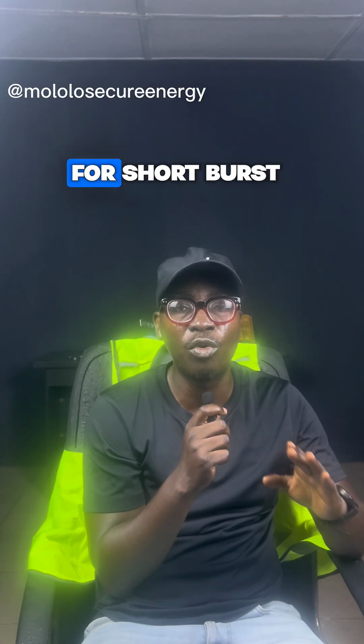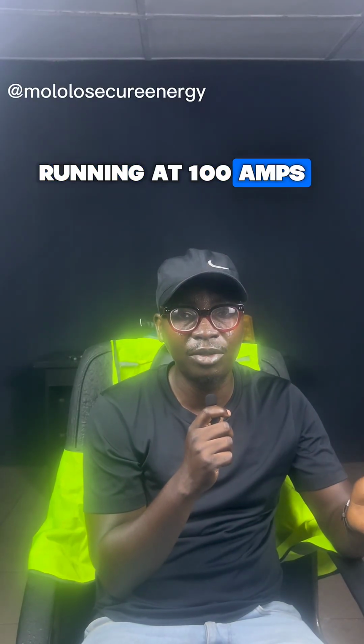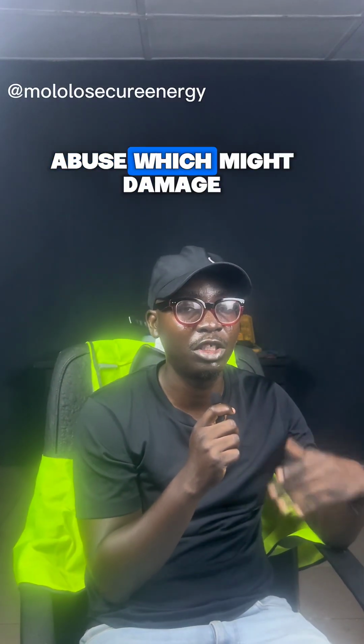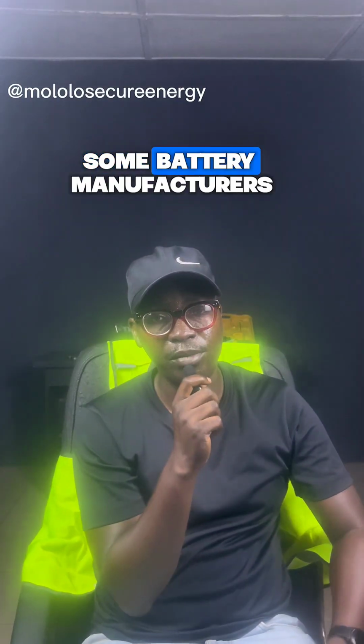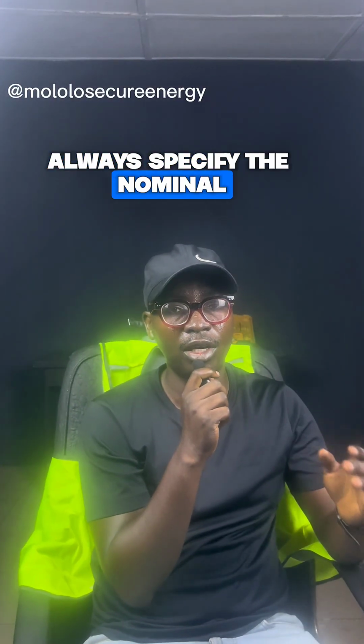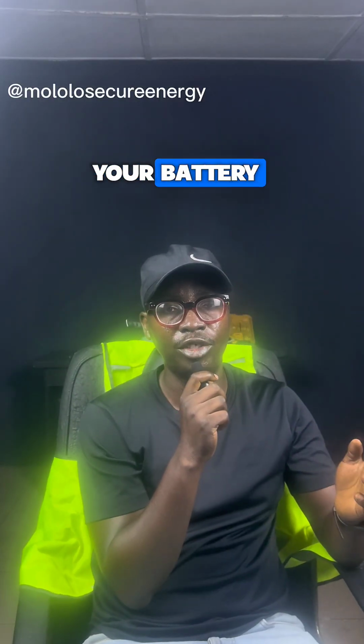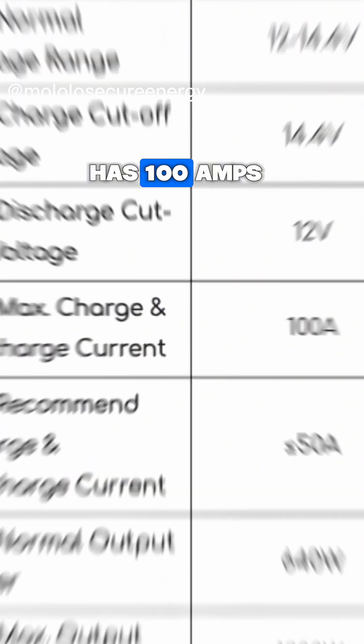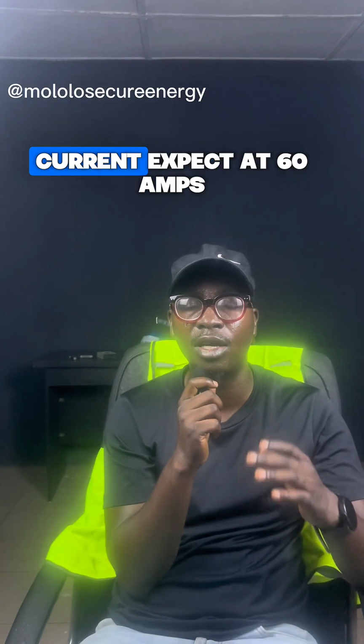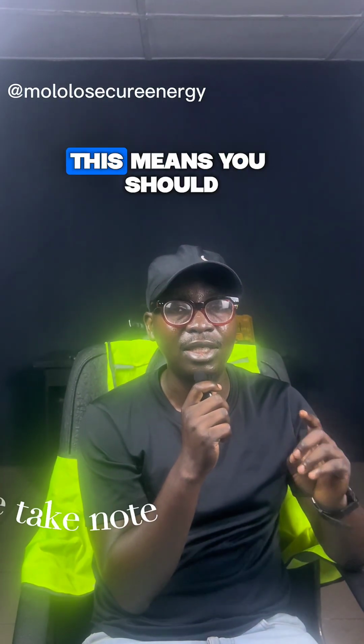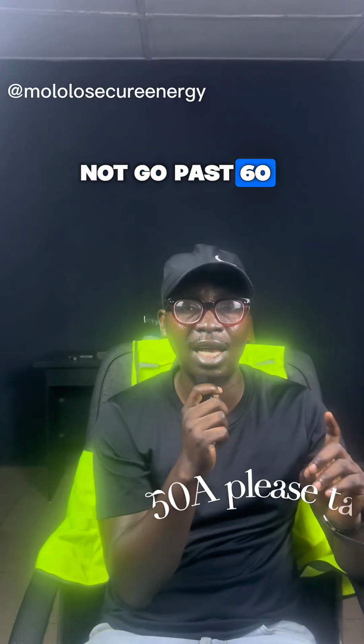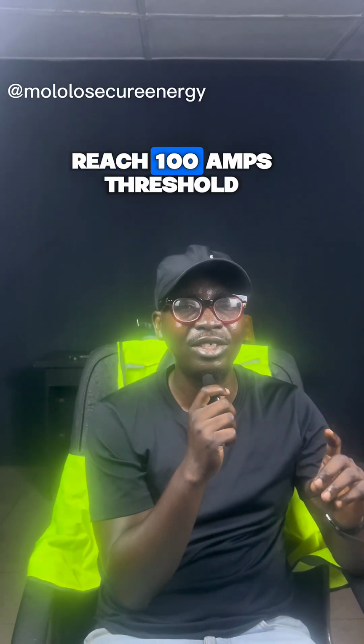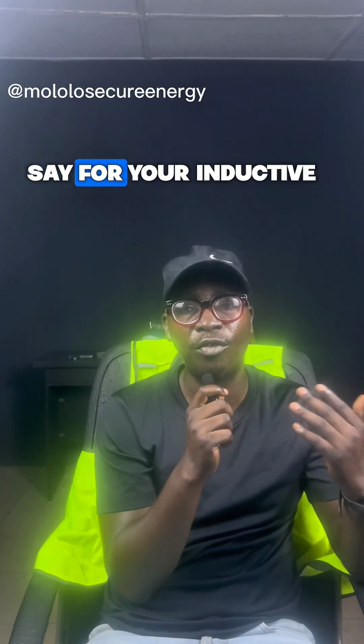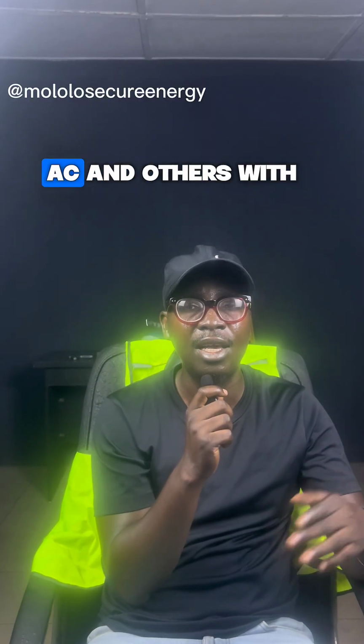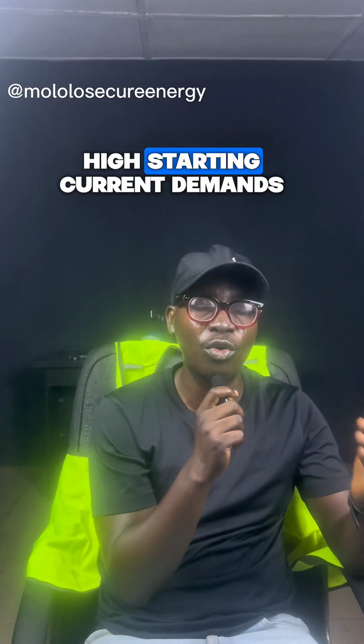100 amps is only for short burst. Running at 100 amps non-stop means battery abuse, which might damage your battery. Some battery manufacturers always specify the nominal operating current you can draw from your battery. For instance, say a 12 volt 100 amp battery has a 100 amp BMS with a nominal current pegged at 60 amps. This means you should not go past 60 amps often, and you can only reach the 100 amp threshold for a few seconds, say for your inductive loads like freezer, AC, and others with high starting current demands.